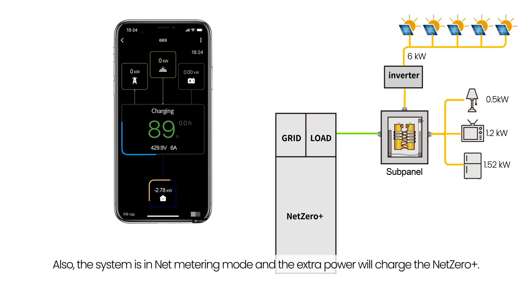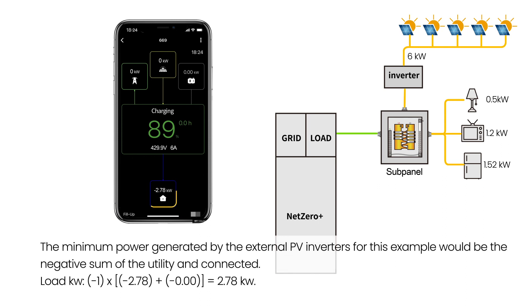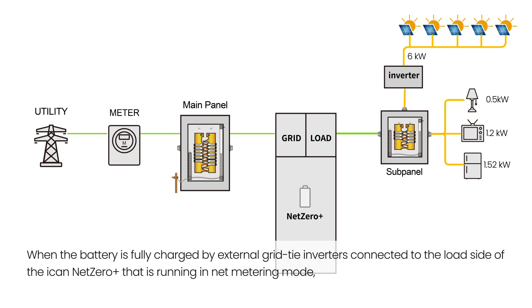Also, the system is in Net Metering mode and the extra power will charge the Net Zero Plus. The minimum power generated by the external PV inverters for this example would be the negative sum of the utility and connected load. The battery is being charged automatically based on the backflow rate. When the battery is fully charged by external grid-tied inverters connected to the load side of the iCAN Net Zero+, it is running in Net Metering mode.